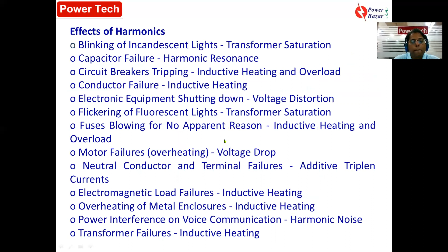Now, similarly, in case of active front-end based VFD, it will have an LCL filter, which is similarly opposite to this, so that we get the harmonics reduced because of LCL. What will happen? You will have some resonant frequency, some tuned frequency. If you have seen any radio, when you match your frequency, what will happen? It tries to take a particular frequency and discard all other frequencies. Because of LCL, inductor and capacitor, it gives lower impedance at resonant frequency.